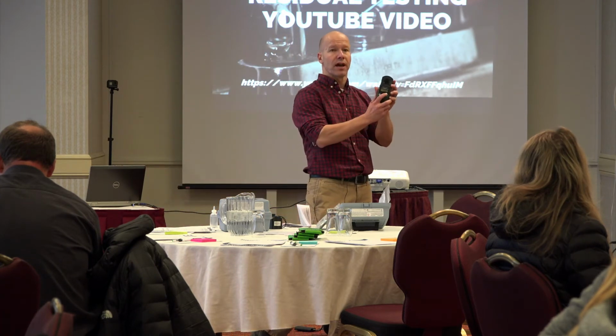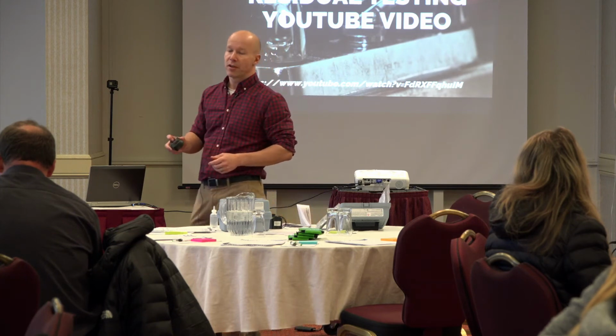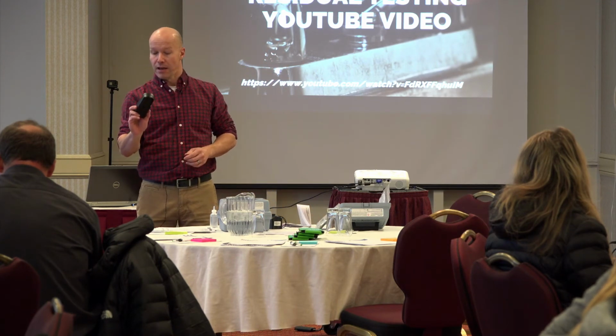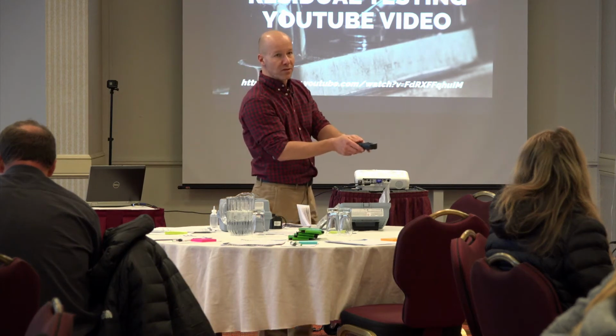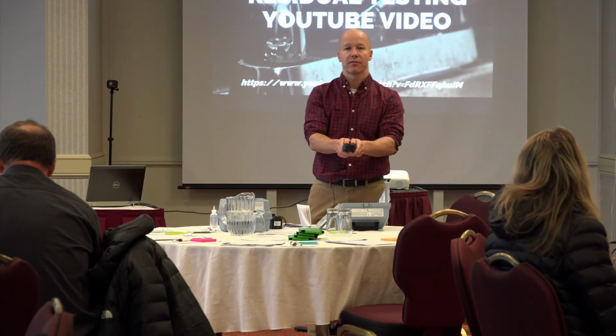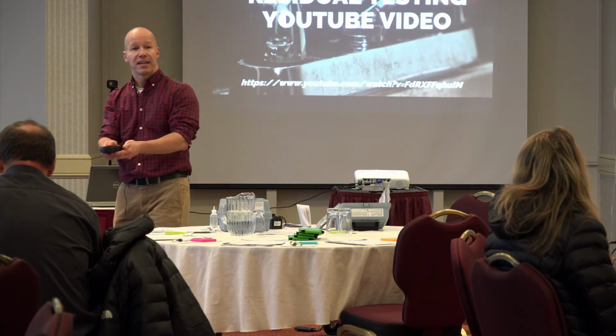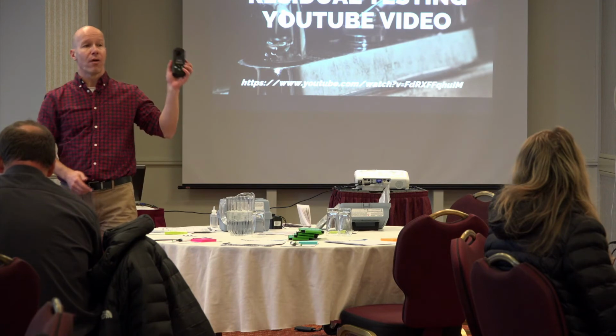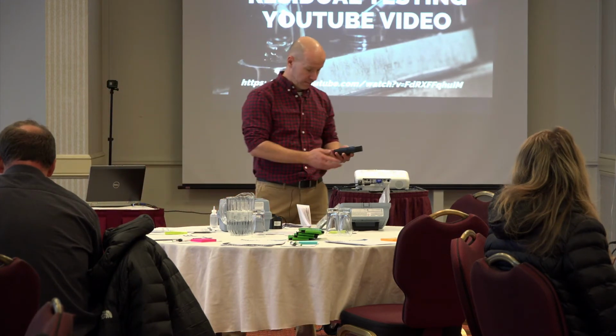So even if you don't have to rely on that little arrow that's there, just looking at the number of digits on the screen will tell you what range you're in. The light blue ones, what you've got to do is there's 2 buttons on that one. You hold both buttons down for about 1.5 seconds, and after 1.5 seconds, you remove your left thumb from the 0 button, and it switches range. So there's no arrow on it to tell you which range you're in, but again, the number of digits will do that for you.